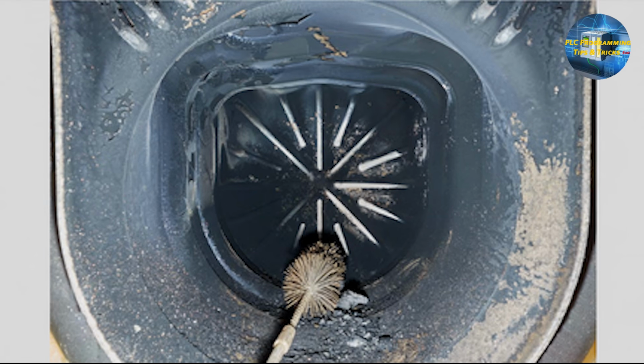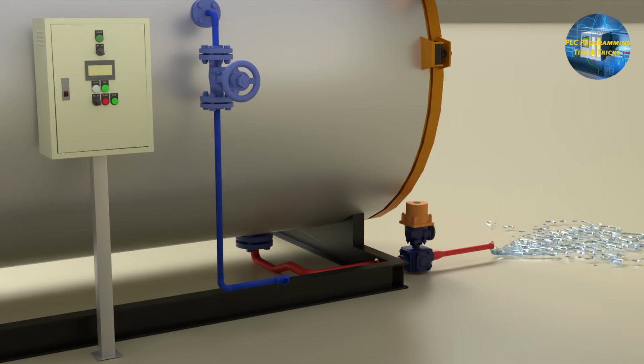This drain valve opens maybe 4 to 5 times a day for a quick 10 to 20 seconds just to drain some water from the boiler. And this helps to improve the boiler efficiency. Draining reduces the risk of internal corrosion caused by settled debris.